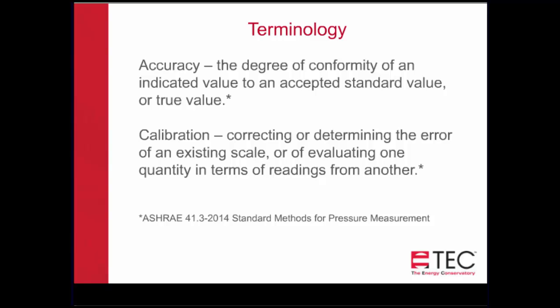Now, calibration is when we correct or determine what the error is of an existing scale compared to readings of another device. So when we know something is 100 pascals, if our instrument is reading 90 pascals, we know that it's 10 pascals off, and that's a calibration or a correction of an existing scale.